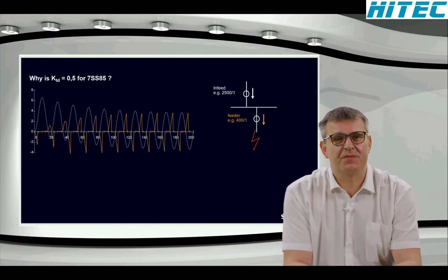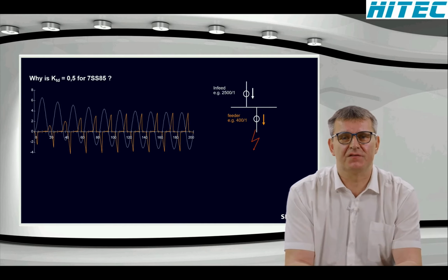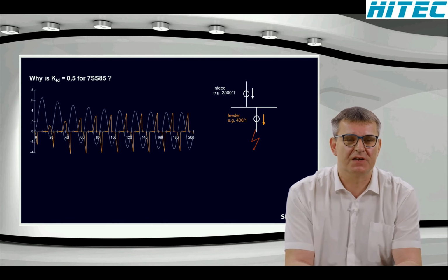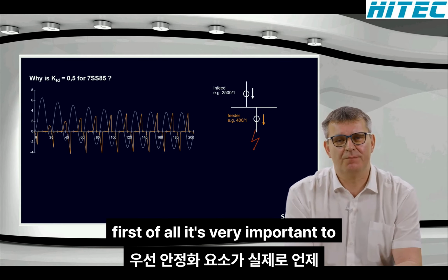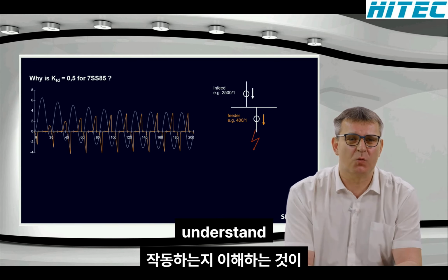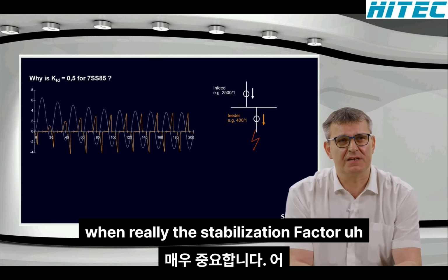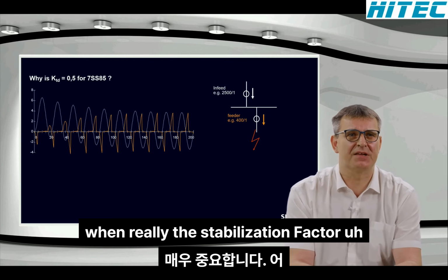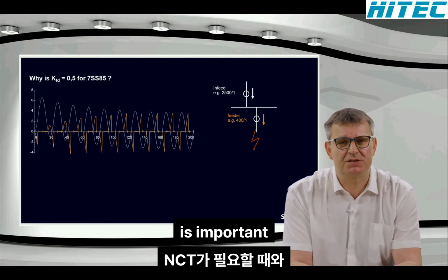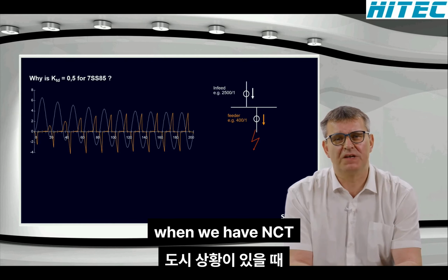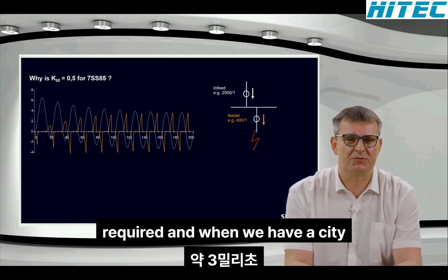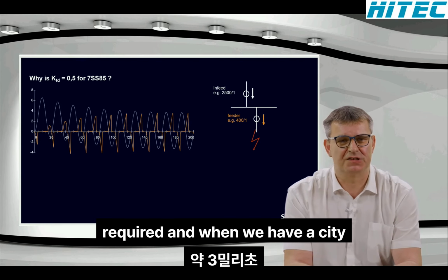Why is the KTD 0.5 for the 7SS85? First of all, it's very important to understand when the stabilization factor is really important: when we have CT saturation.